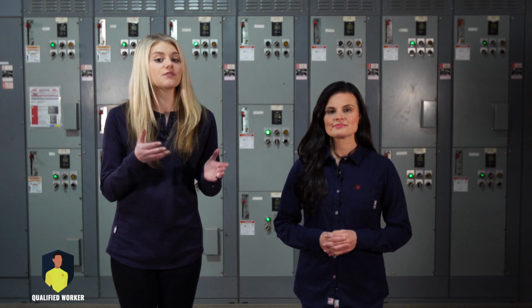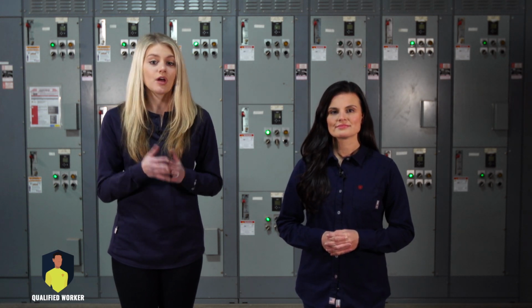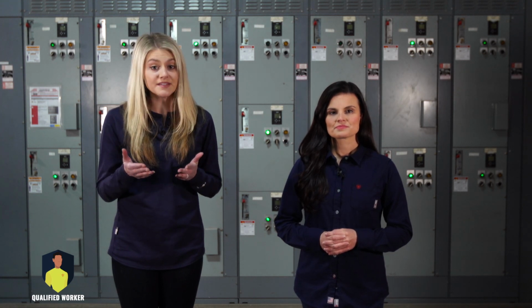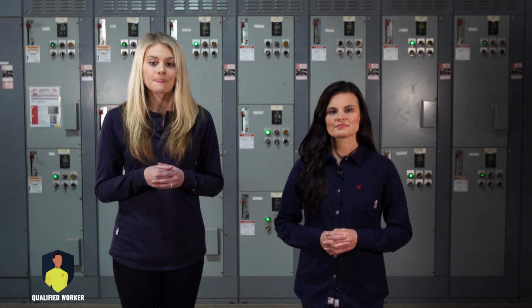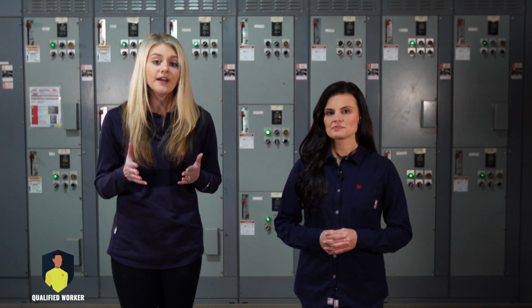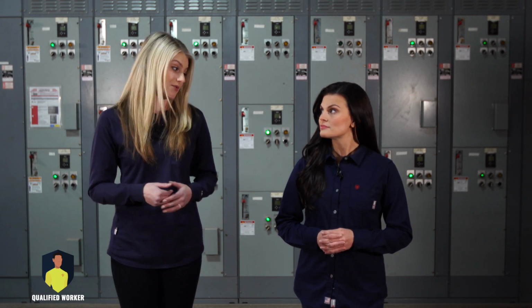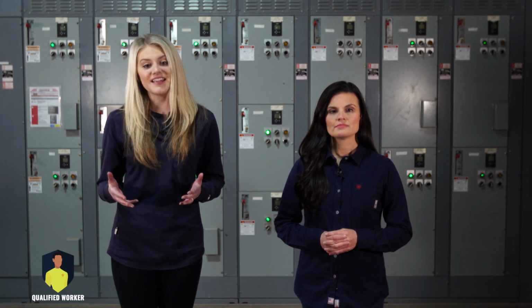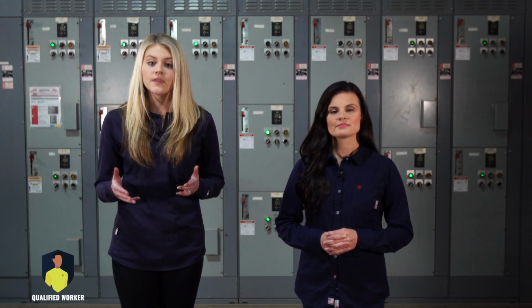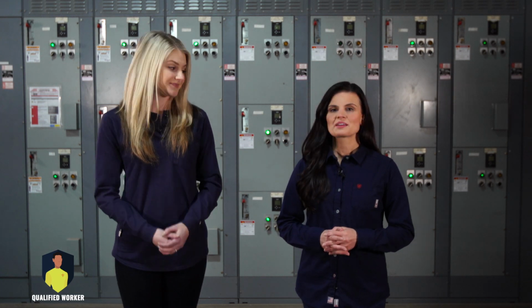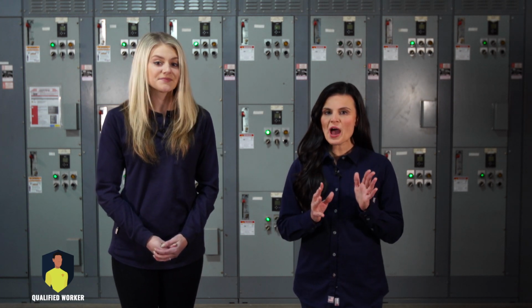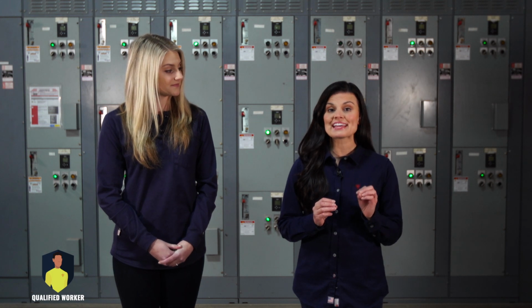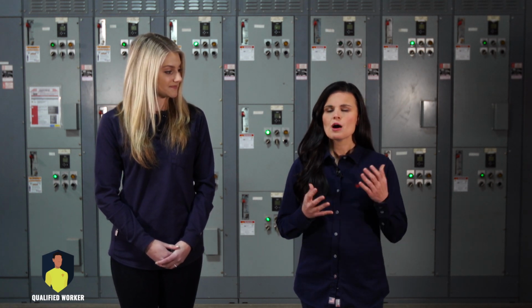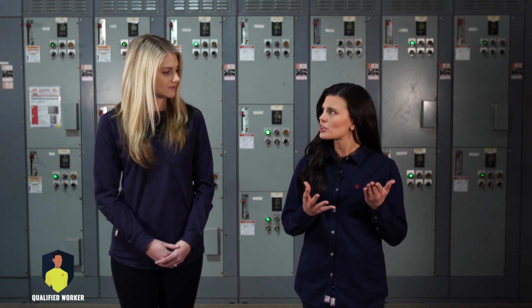T stands for tags and locks. Apply them to all protected devices for isolation. And A stands for absence of voltage should be verified using adequately rated test equipment. And G stands for grounds. Safely apply them in the area in which you're working. So, you know how to create an electrically safe work condition. But what do you do when you have to work energized?